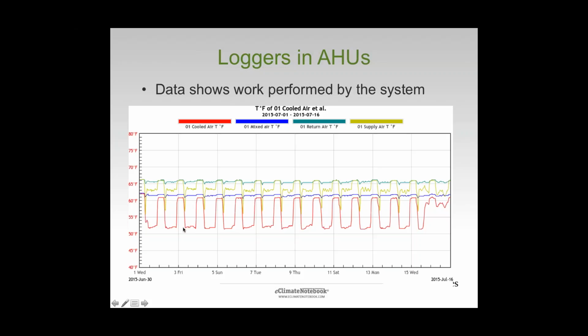Not only do we see that the cooled air on a normal basis might be creating, let's call it 52 degrees when it's turned on, but we also see that we have this pattern in the cooled air plot. And that tells us, well, maybe there's a shutdown going on, or there's some other factor of control that's being put in here. And as we start to dive into this operation a little bit more closely, we want to find out what's causing this particular swing in air condition at that cooling coil.